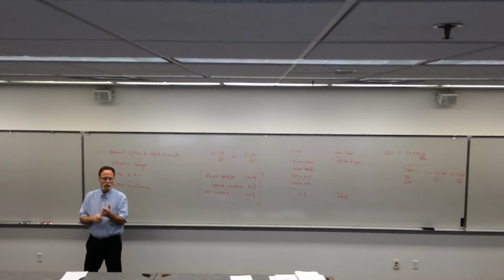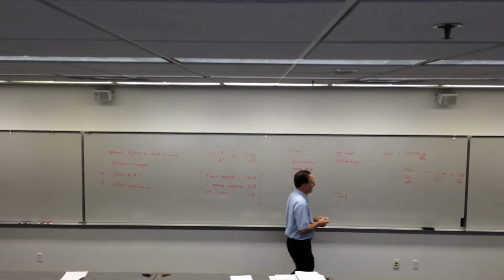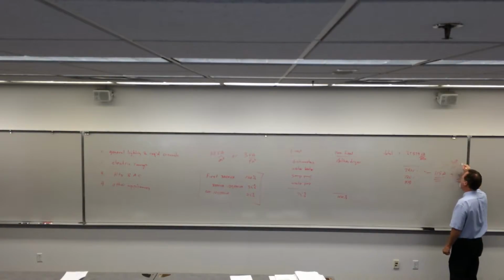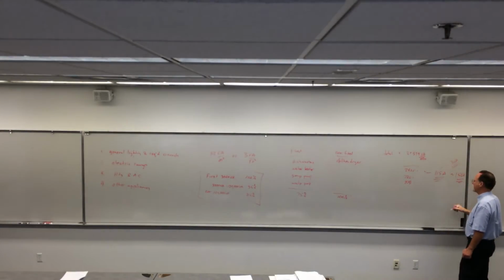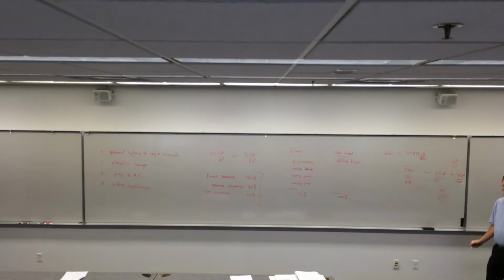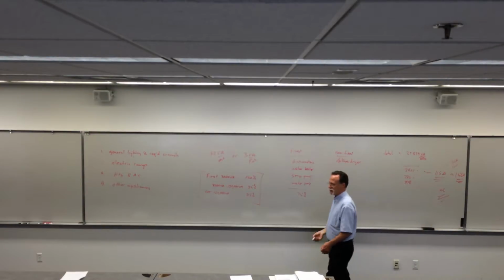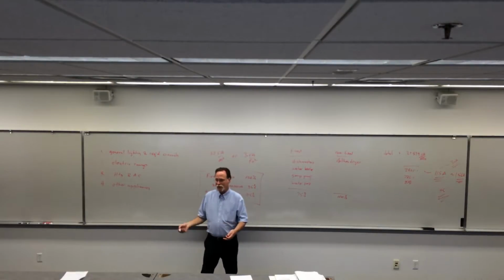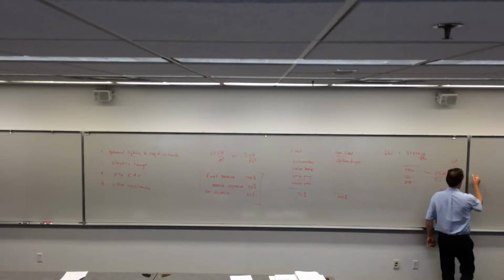I can save 50 bucks if I go with the smaller size, but I will have no option. I can't add anything. So think about it. If I know I'm going to have a 30 amp welder put in my garage, and I want a special circuit for that, that brings me up to 145 with nothing to spare. No addition. I'm a young family. I might have kids. It's a three-bedroom house. I might have 3 bedrooms and an office. I need 4. That'll be expansion. So, geez, long-term planning. I'll put a 200 amp box in here.